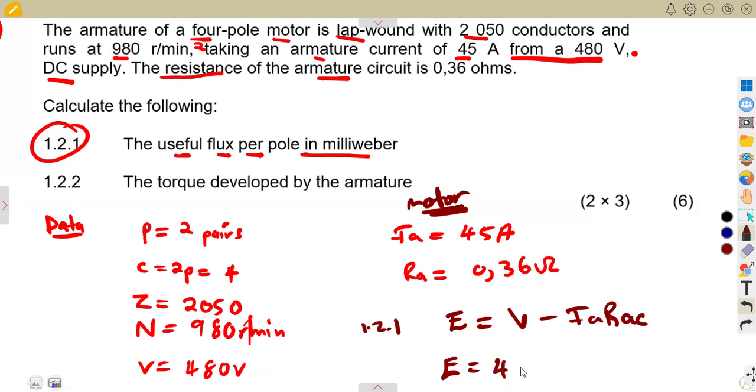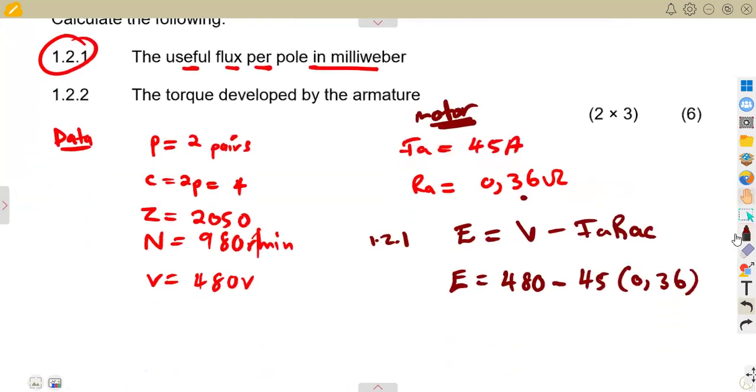So this is everything in the armature circuit. We can have the generated EMF. The voltage we are given 480, the armature current 45 amps, then only a single resistance 0.36 ohms that we are given in the armature. So we are going to have our E as 463.8 volts as the generated EMF.